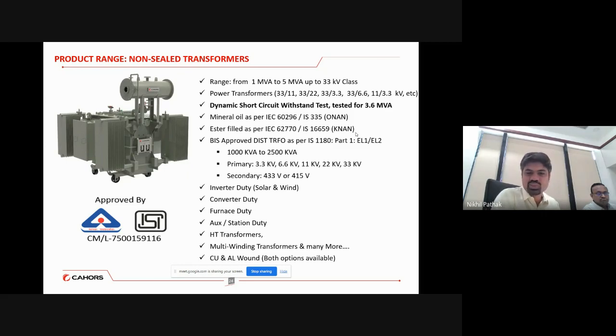So it can be small power transformers for 5 MVA, 33/11, and 3.3, 6.6 kV, as per the requirements of the customer. For this product line, we have type testing done up to 3.6 MVA, and the BIS transformer range that we have is 1 MVA to 2.5 MVA. I'm sure India has all the voltage classes: 3.3, 6.6, 11, 22, 33. So all these ratings we are covering for the BIS standard also. Along with that, inverter duty, converter duty, furnace duty, auxiliary station transformers, HT transformers, multi-winding transformers, all different types of applications we are also catering to.